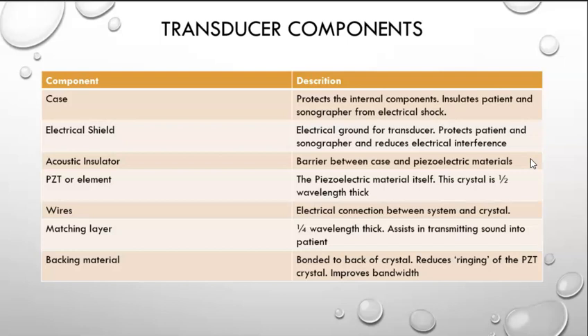There is the PZT, or element itself, the crystal, which is the piezoelectric material itself, the actual crystal that's going to be causing the electrical signals back to the machine or the sound to go into the body. The crystal is a specific size. It is called a 1/2 wavelength thickness of the crystal. And when they talk about the wavelength of this 1/2 wavelength, this wavelength is the wavelength of the sound in the crystal itself. So you can imagine a crystal being a hard rock. It's going to be much faster propagation speed than the human body. So that's where the half thickness comes from, is the measurement of the crystal of the piezoelectric material itself.